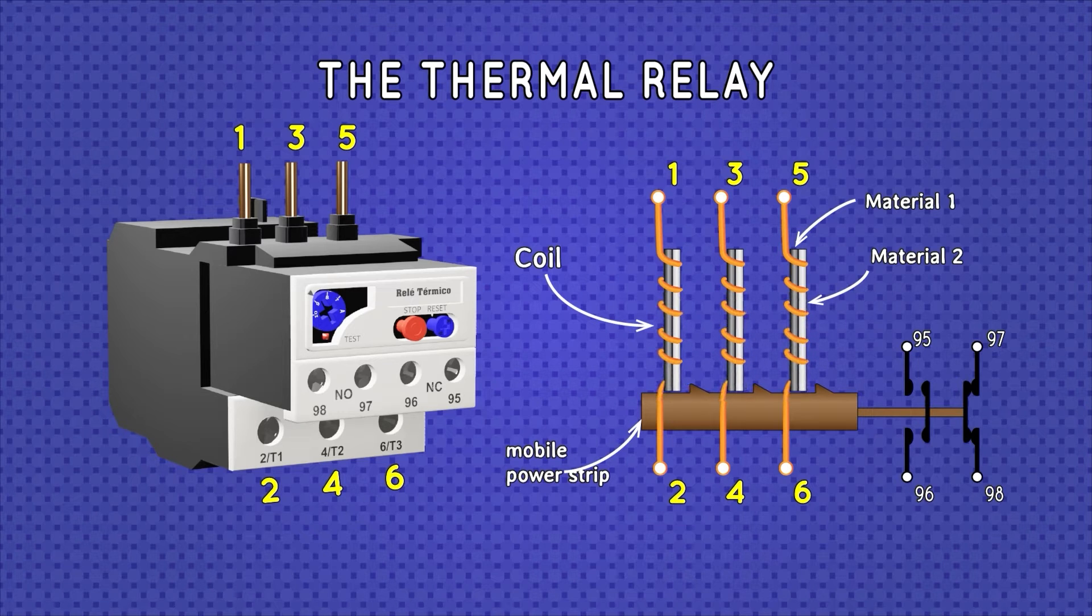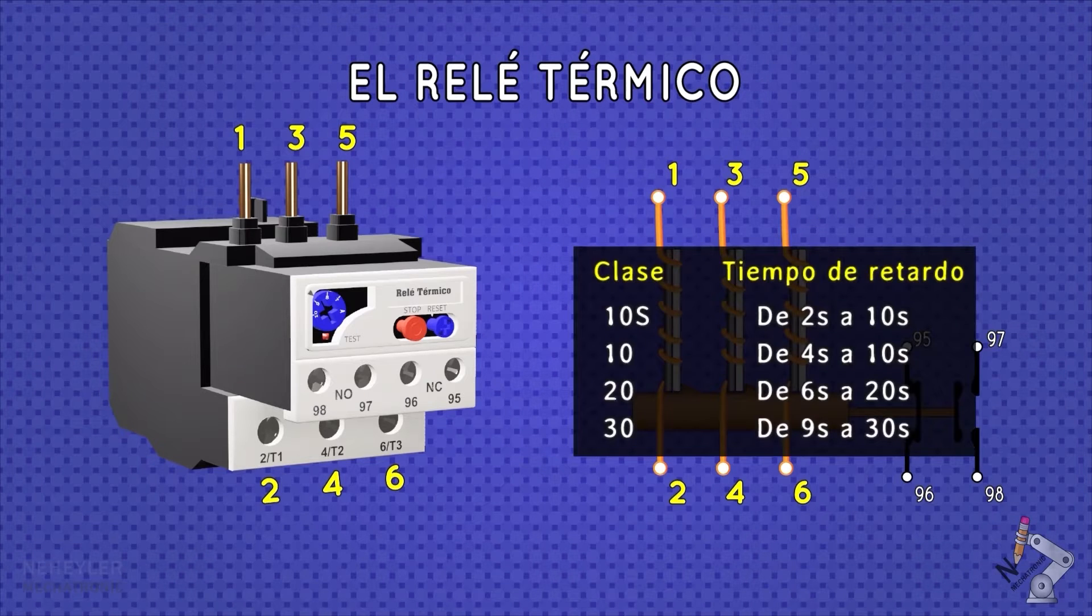These will return to their initial position automatically if the reset button is in automatic mode. Otherwise, you have to press the button manually to reset its contacts. The time it takes for the relay to generate the trip depends on the class to which it corresponds, which is shown in the table.